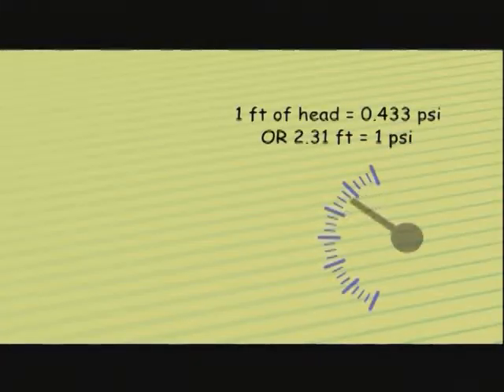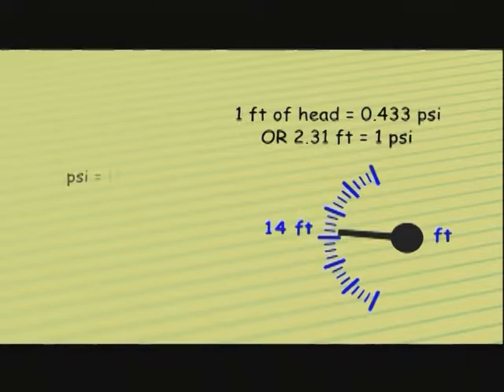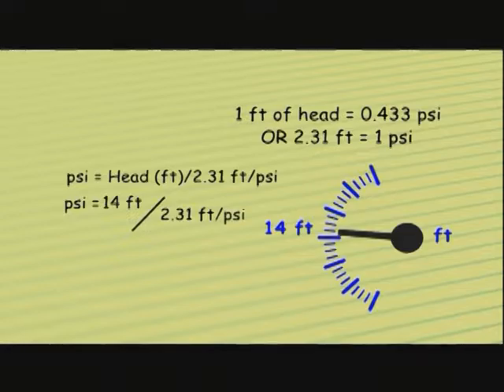If we have a pressure gauge reading of 14 feet, how many PSI is that? We take the 14 feet divided by 2.31 feet per PSI. The feet cancel out and we are left with 6.06 PSI.